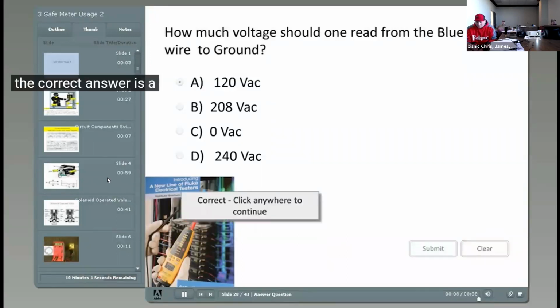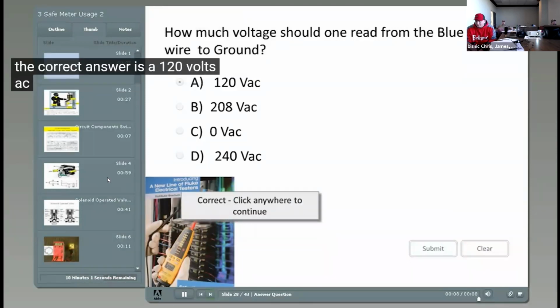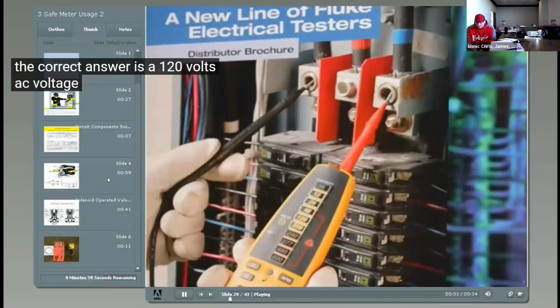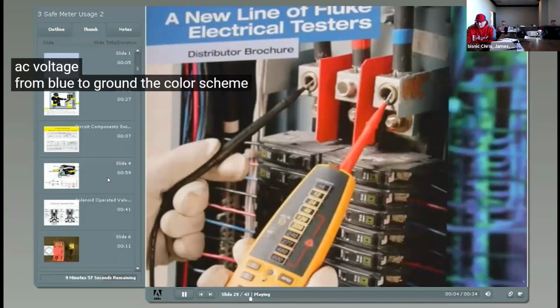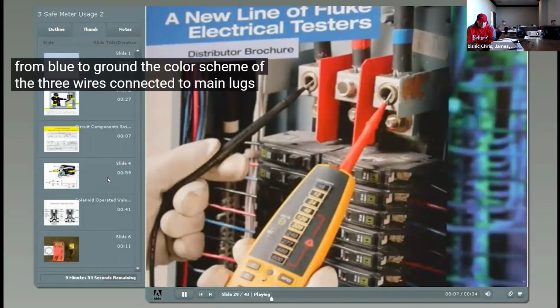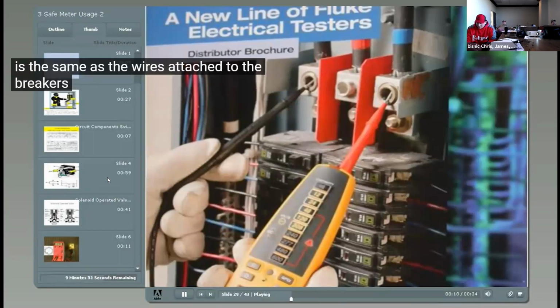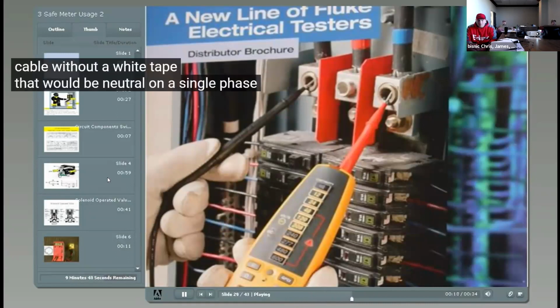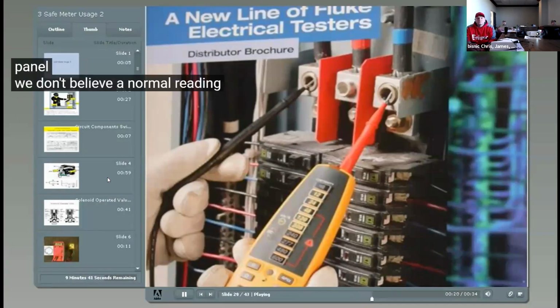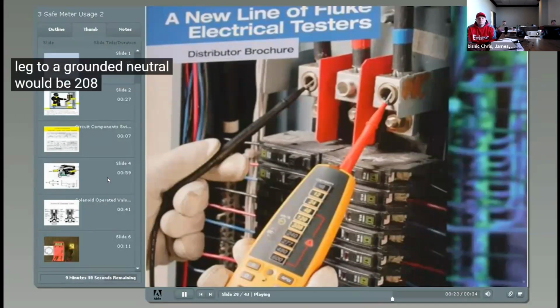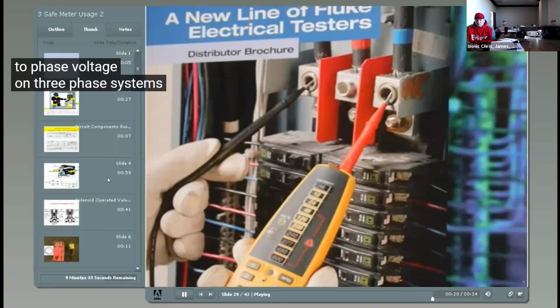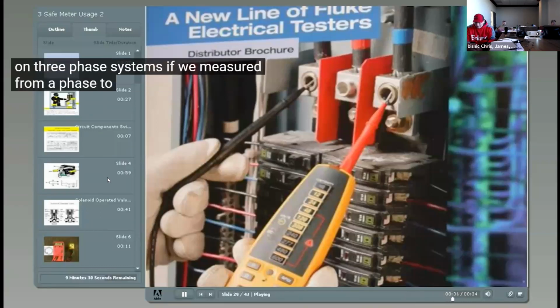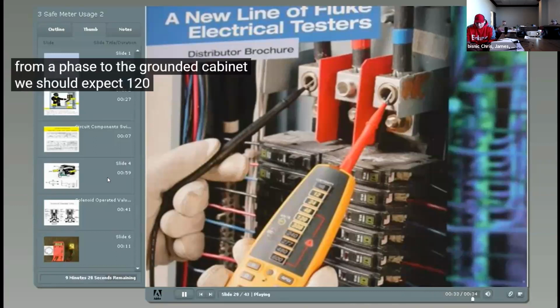The correct answer is A, 120 volts AC. Voltage from blue to ground. The color scheme of the three wires connected to main lugs is the same as the wires attached to the breakers, indicating three-phase. Therefore, the hidden cable is truly a cable without a white tape that would be neutral on a single-phase panel. We don't believe a normal reading from a leg to grounded neutral would be 208 volts. 208 volts is a phase-to-phase voltage on three-phase systems. If we measured from a phase to the grounded cabinet, we should expect 120 volts AC.